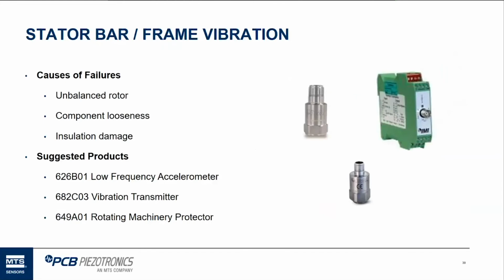Stator bar frame vibration. We've seen failures due to unbalanced rotors, insulation problems, looseness. The bars get loose and start causing noise. I've been in plants where I can hear the looseness of stator bars.